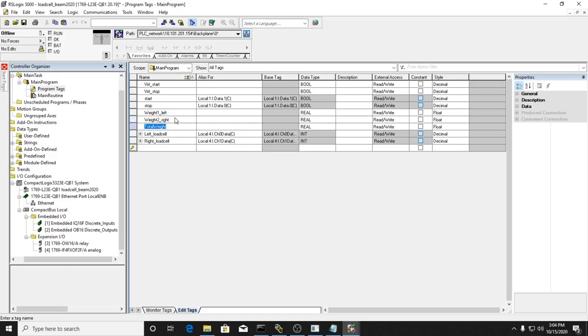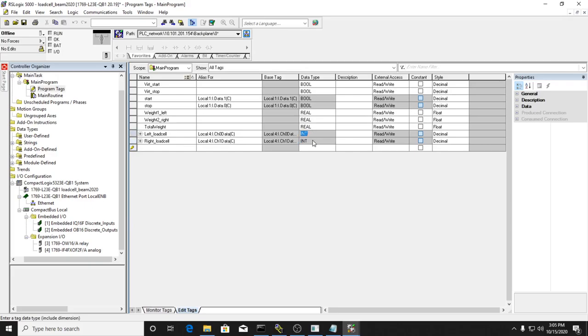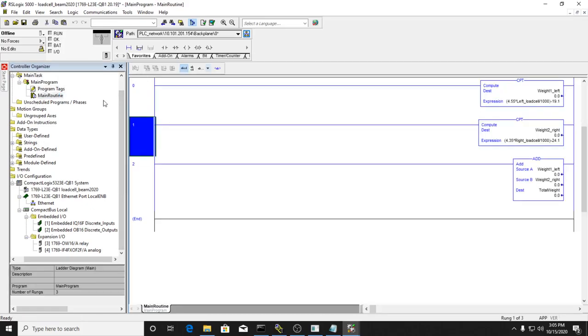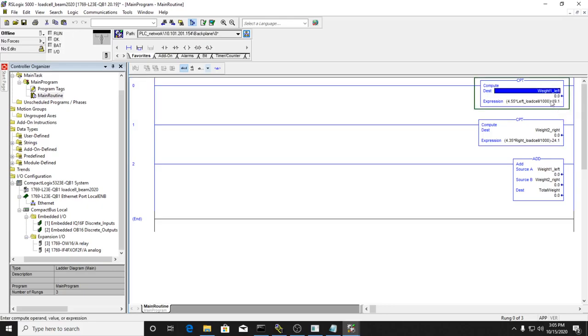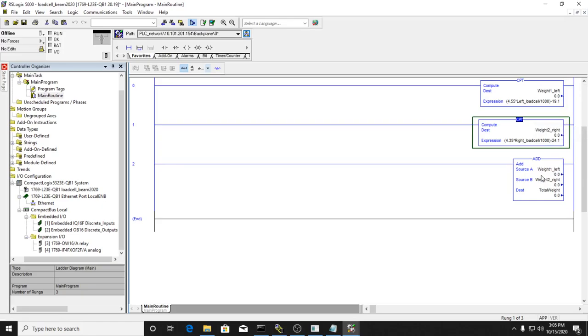I also created three floating point real decimal point variables: weight left, weight right, and total weight. We've got two load cells making up a little balance beam weighing system - one on each end. Weight one is on the left side, weight two on the right side, and the total weight will be their sum. I also created tags for the actual analog inputs from the load cells: the left load cell on channel 0 and the right load cell on channel 1. Those are integers but the value coming in will be a micro amp value.